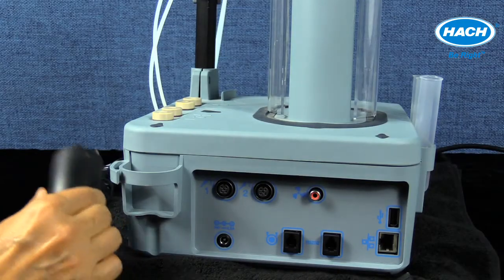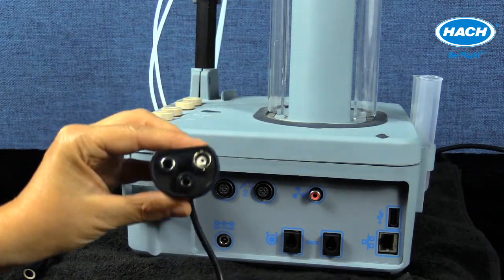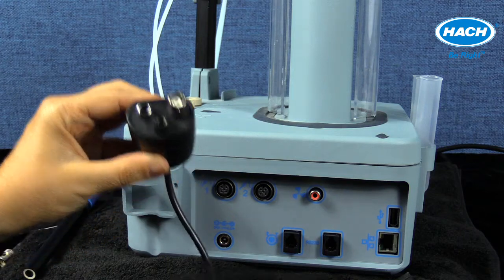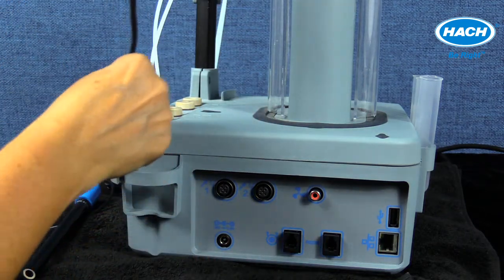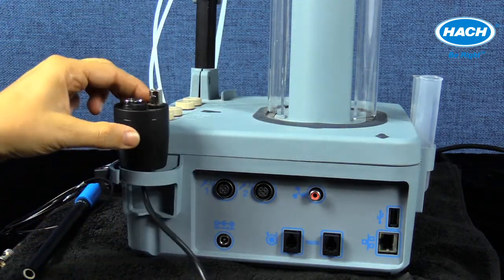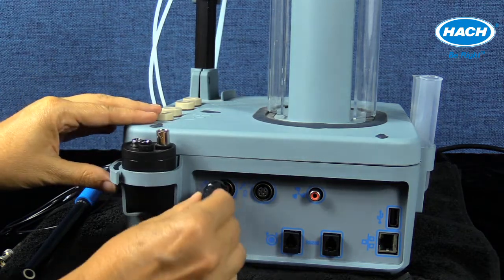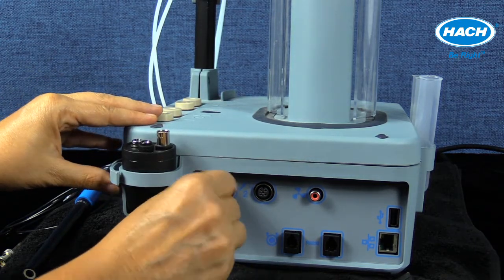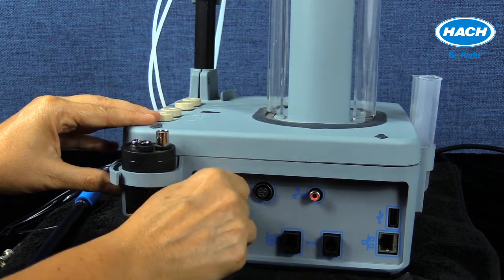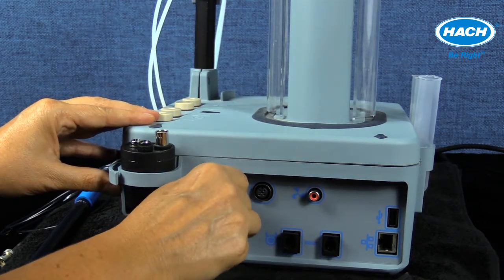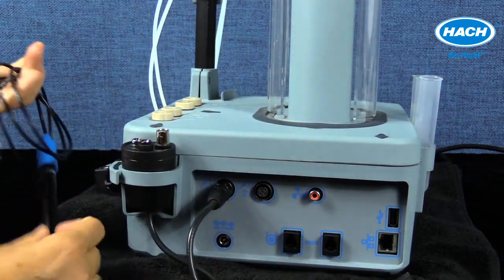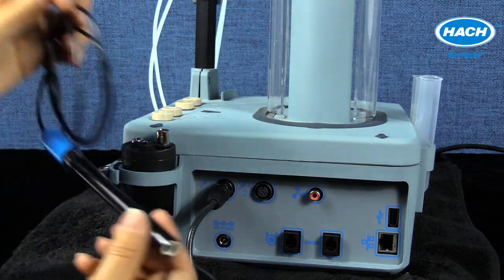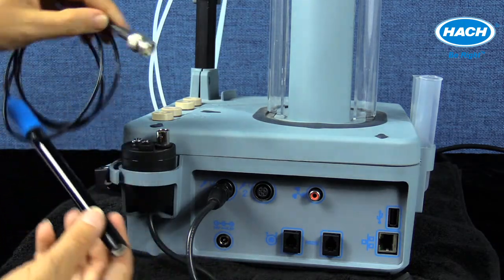The legacy sensor adapter and holder is used in application kits that call for a sensor that is not from the IntelliCal product line and has an M12 digital output connector. In this example, the legacy adapter is plugged into sensor port 1, and a BNC ISE electrode is connected to the adapter.